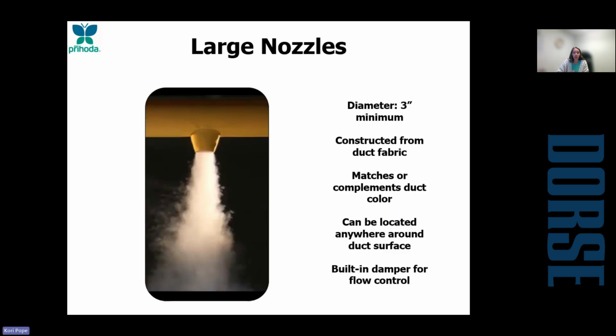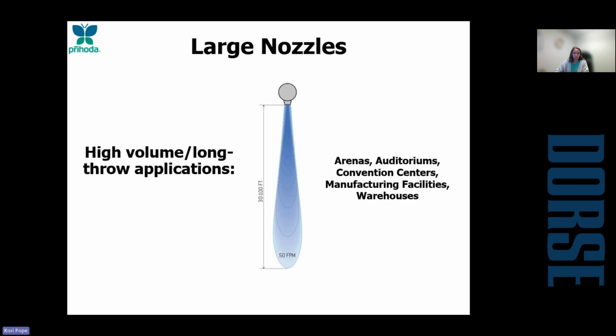So when we really need to get that air moving a long way, like in any type of big manufacturing facility, we're going to jump up to our large nozzles. Our large nozzles have a 3-inch diameter minimum and are again constructed from the same fabric that our ducts are. One of the cool things with our large nozzles is they come with a built-in damper inside of them, so you have a little more control of the air once the duct gets on site. Our large nozzles are going to be used for high volume, long throw applications when you need to get throw distances of 100 feet or more.